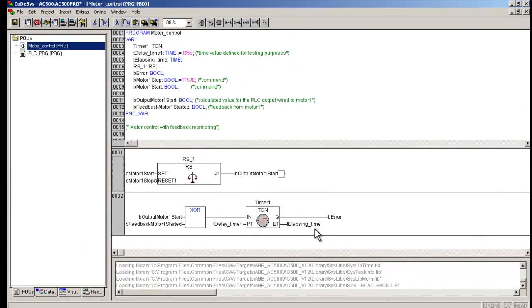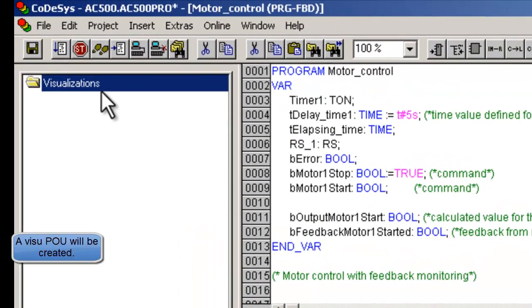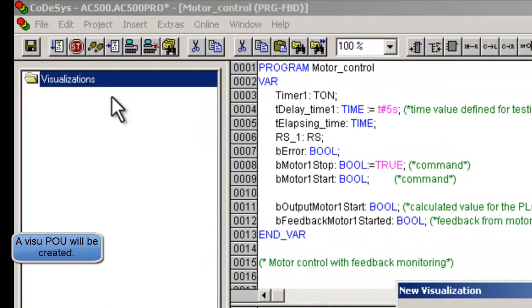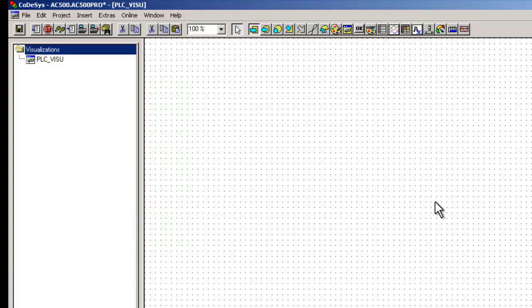In order to create visualization screens, one needs to click on the visualization tab in the CodeSys editor. Let's create a visualization POU using the add object function. One POU will have only one screen, and we could create as many POUs as needed in the same way. The start picture POU must have the name PLC_VISU, and the pictures or pages could be linked to this main screen for better navigation.